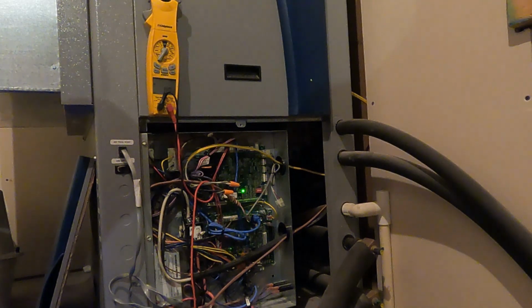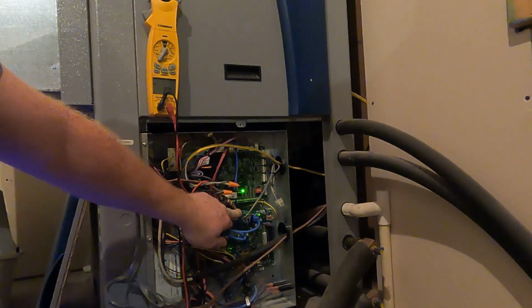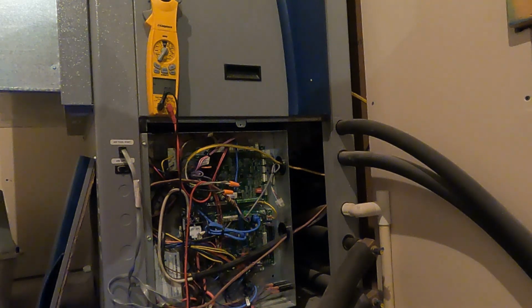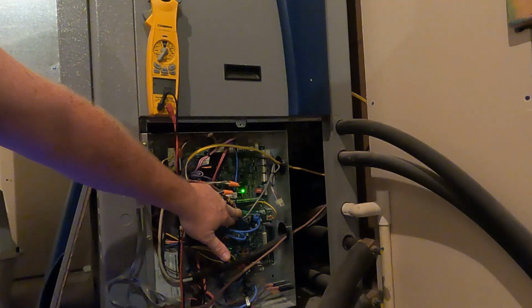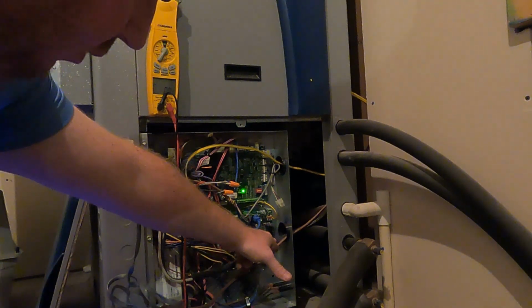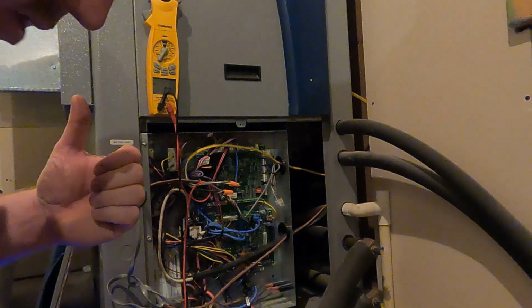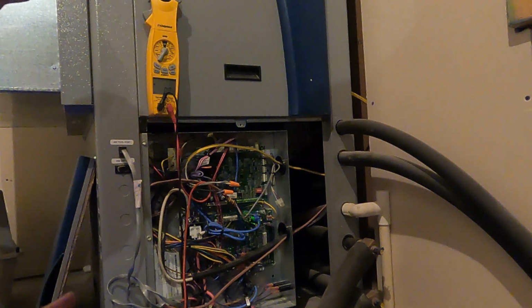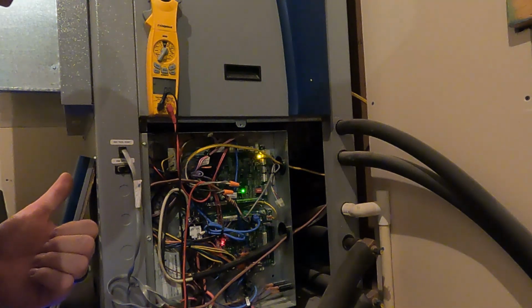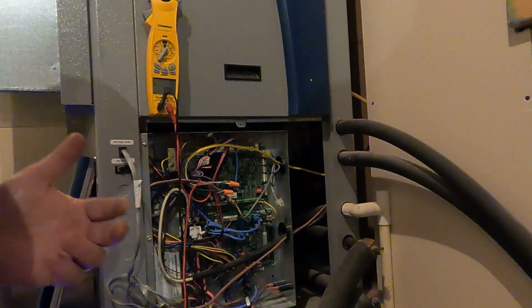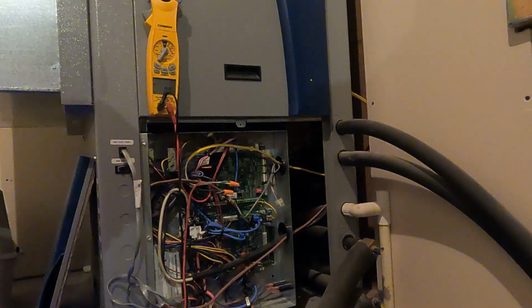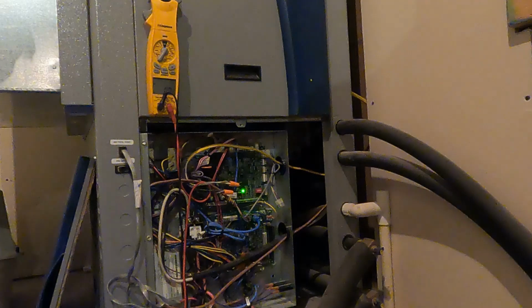Alright, I took a look at the thermostat. All the wire connections are good. This thermostat is a communicating stat, but also can be controlled with 24 volts. Right now it is hooked up in a communicating configuration. So to test this thing out, I'm going to unwire the communication part of it and wire it up to the traditional 24 volts over here, and I'll do the same on the thermostat, test it out, see if it runs. If it runs, could be something internal wrong with that communications on the thermostat or on this board. If not, I'll go ahead and try to change the thermostat out with another 24 volt controlled thermostat, and we'll go from there.